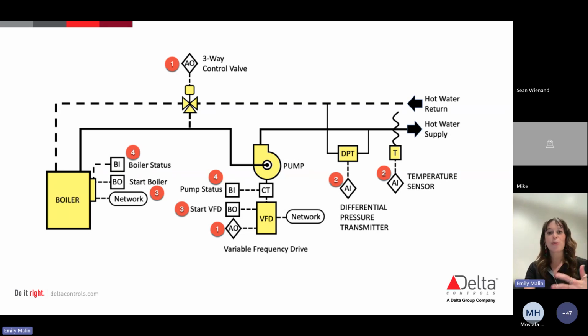So again, you can just go through this diagram and see how all of these things are working together. You'll have a bunch of field devices in here as well. We have thermometers, pressure gauges, and we talked about a few of those, flow switches, as well as all of these valves that are turning on and off based on that control program that says we need more water or we need less water. Included in this as well, I know Moose talked about this, were safety devices, right? We need pressure relief valves and high temperature limit switches to prevent equipment damage or even just unsafe conditions, right?